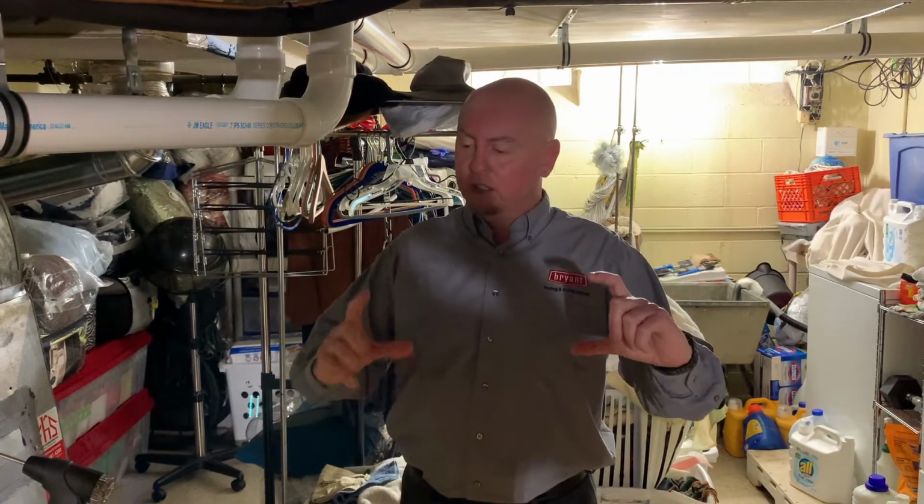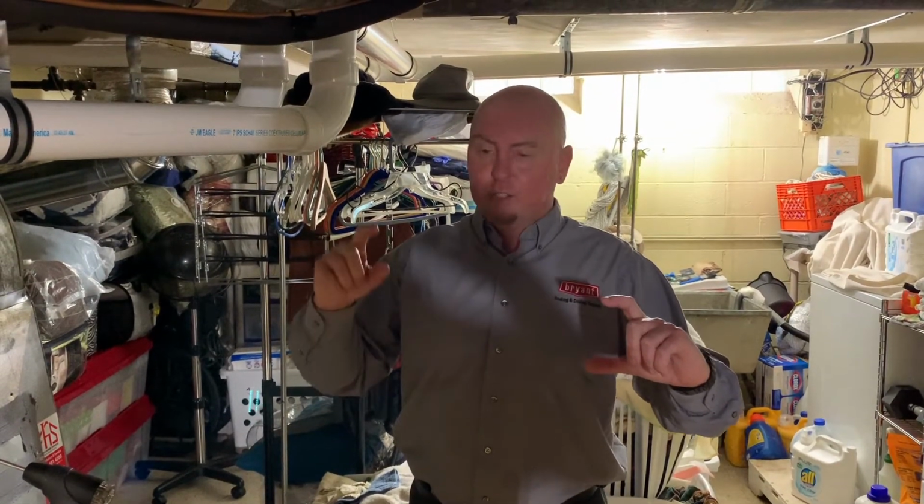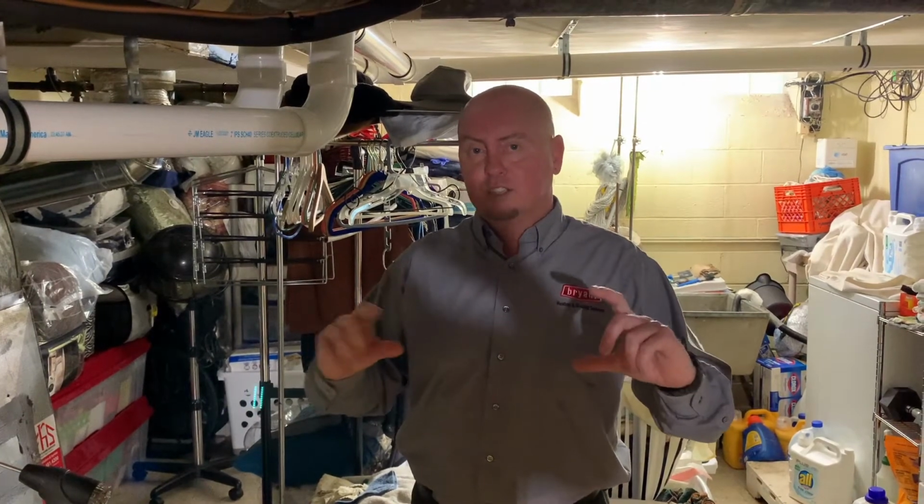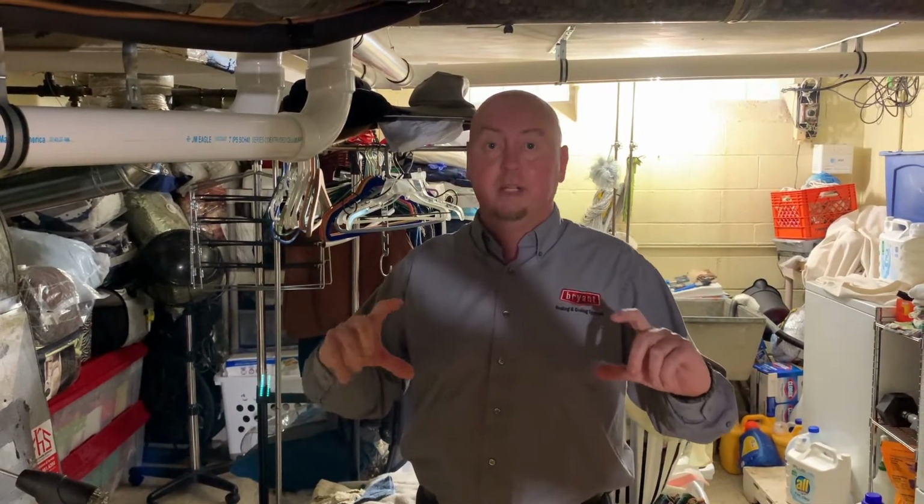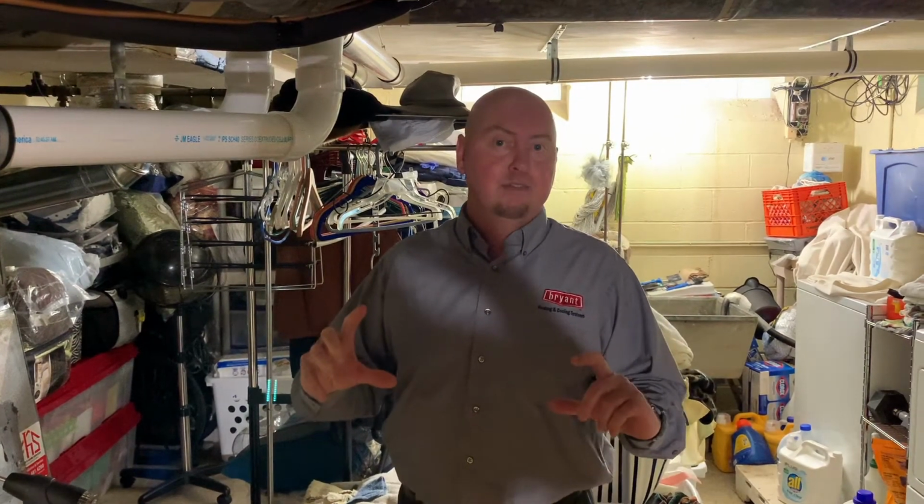Think of it like this. If I have 2 cups of coffee, 8 ounces of coffee here, 8 ounces of coffee here, and I add cream to one of them, I still have 8 ounces of coffee in each one, but the one with cream is diluted with cream. That is ambient CO. It's diluted. We don't care about that when we're checking inside the flue pipe of an appliance. We care about the black coffee, pure CO. That's what we want to look for.